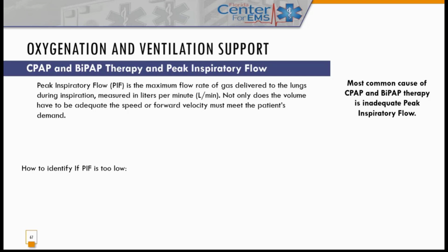So that's what I would want to know, is if I put somebody on device X and they tell me to put it on 8 liters, 10 liters, or whatever they're going to tell you, what's the peak flow coming out the other end? Because if you're not getting close to 65 liters a minute, that's not the volume, even though the venturi does add to the volume. It's the speed that I want. And so if you look at that manometer and you got it on a patient, and every time they inhale, it goes to 0. First of all, you're not CPAP and BiPAP anymore, because pressure is supposed to be continuous. So I lost that. And now I'm not giving it fast enough.